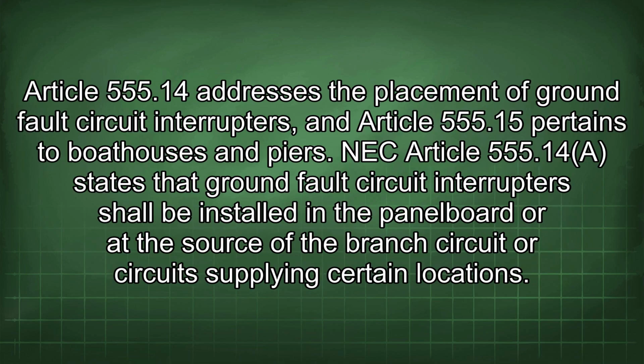Article 555.14 addresses the placement of ground fault circuit interrupters, and Article 555.15 pertains to boathouses and piers. NEC Article 555.14 states the ground fault circuit interrupters shall be installed in the panel board or at the source of the branch circuit or circuit supplying certain locations.